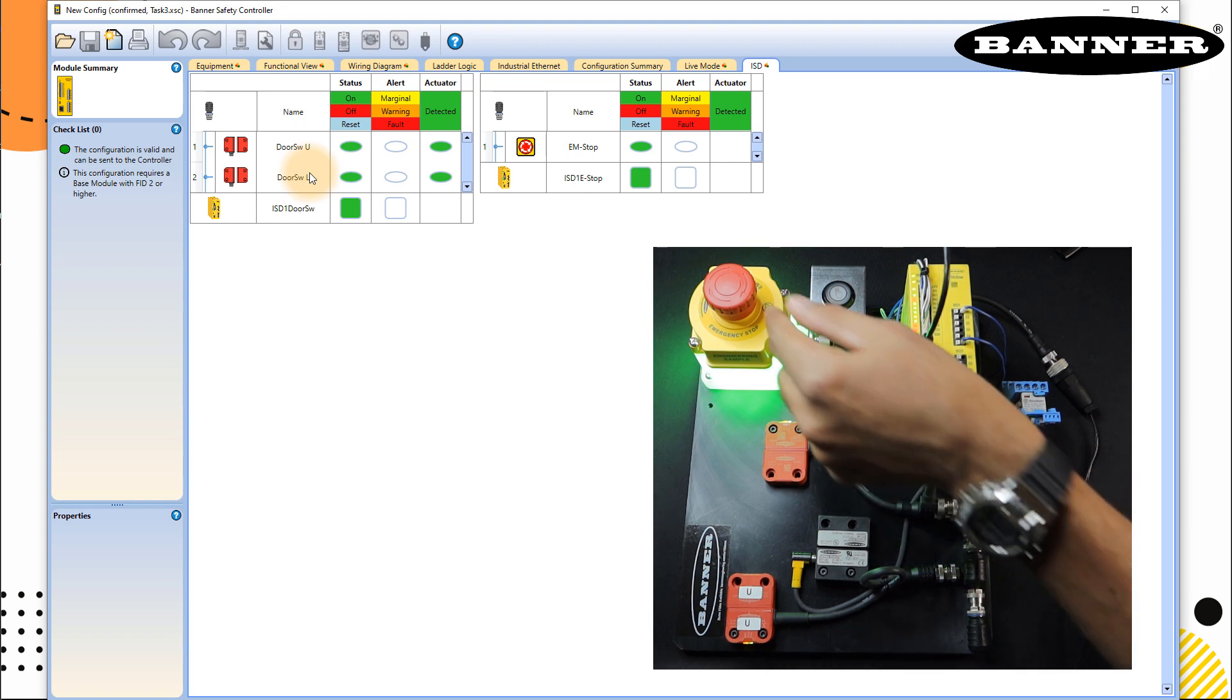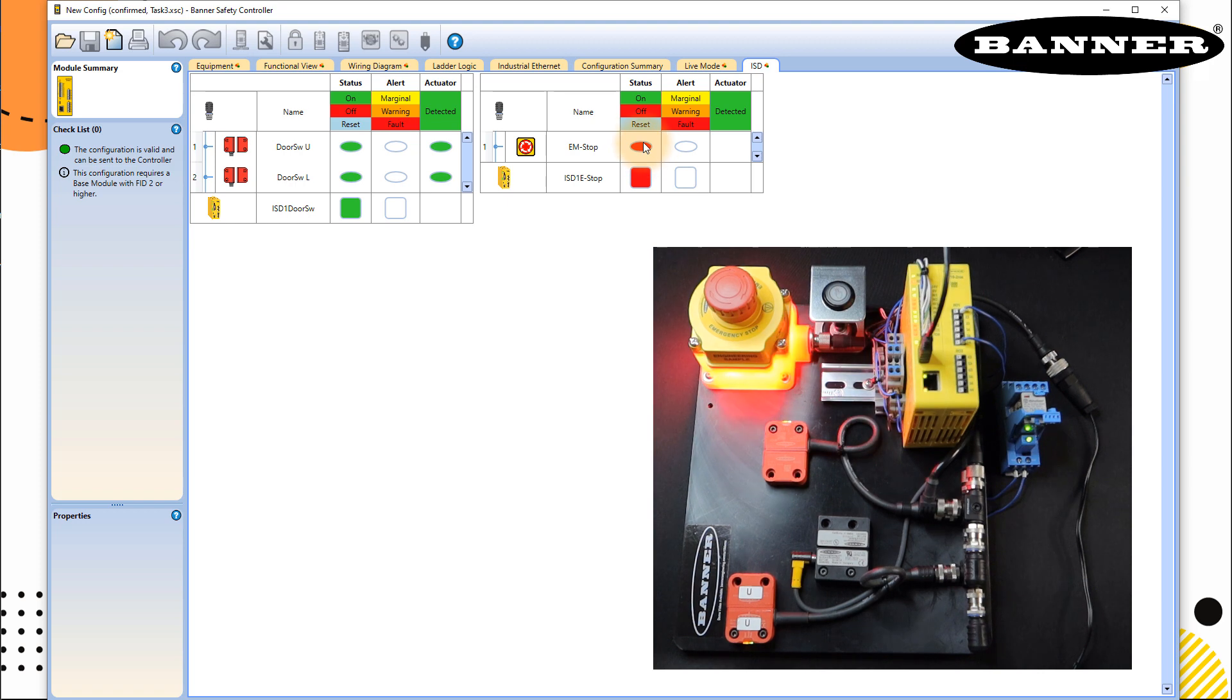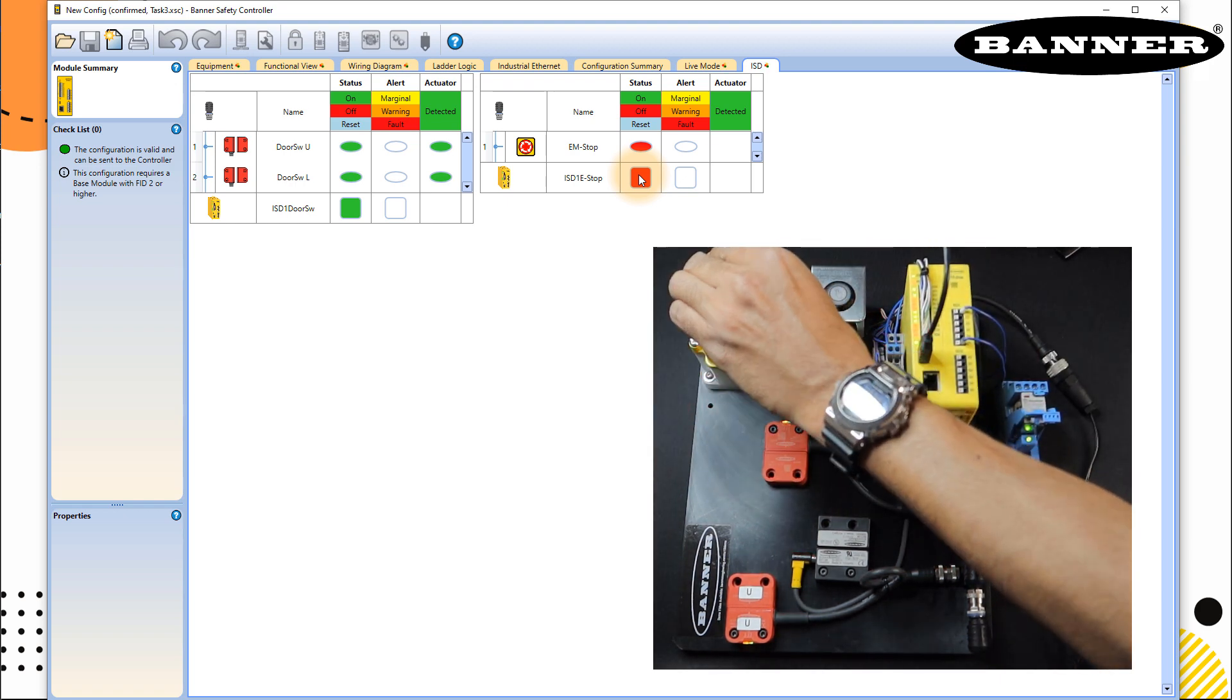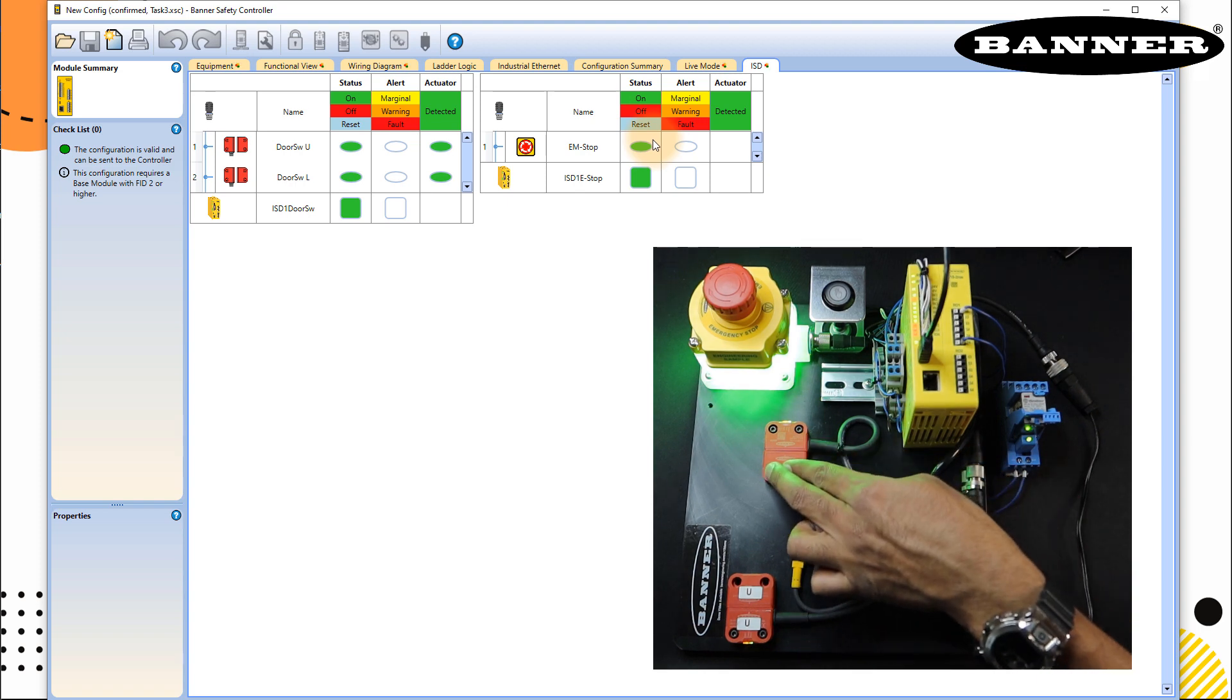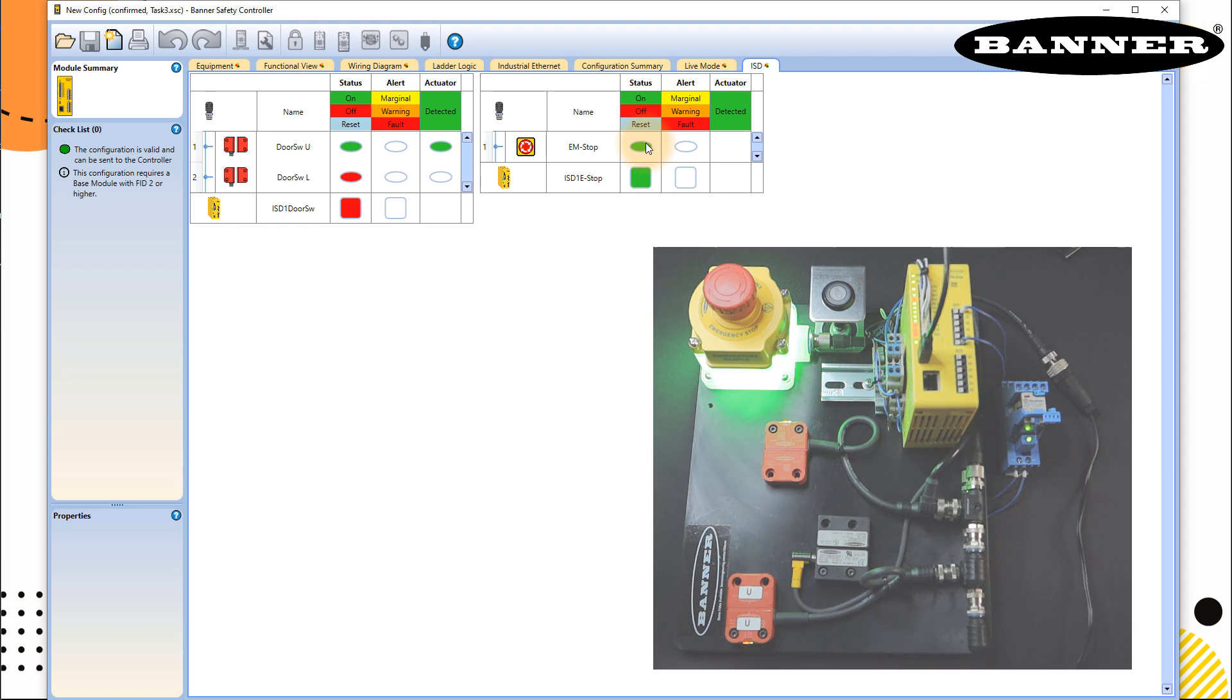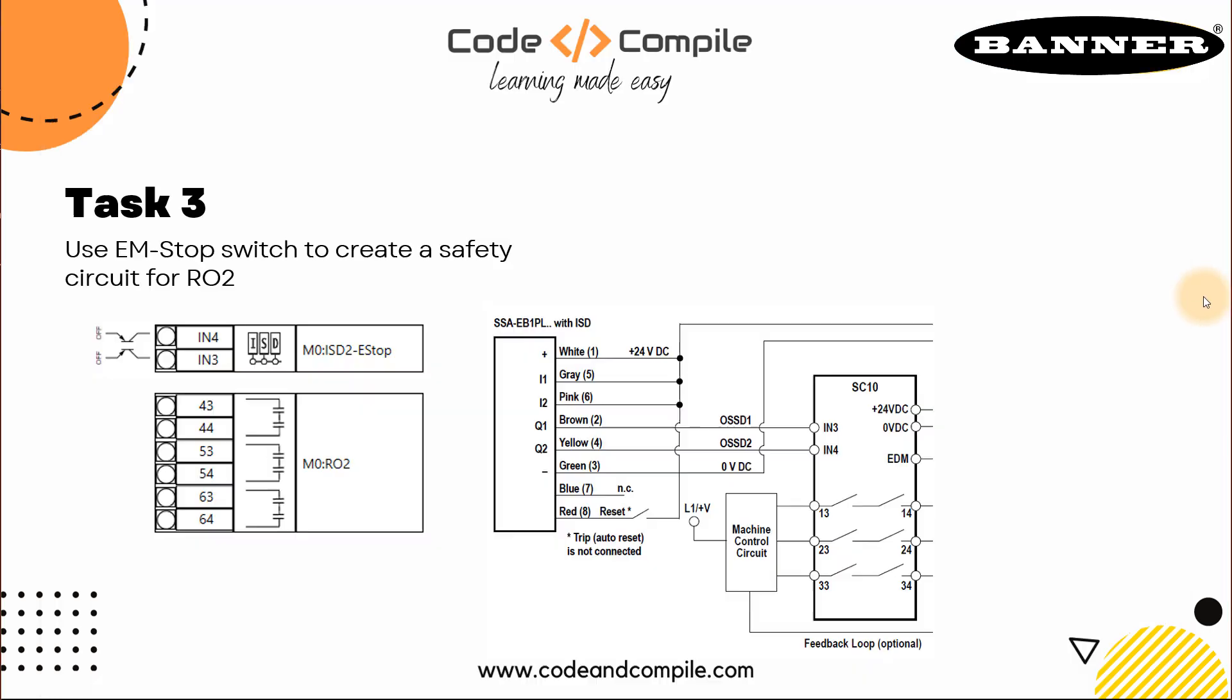Once again, if you press the E stop here, you will see the signal in the E stop is getting red. So ISD chain is false and my RO2 is false. I can release it to see the status back on my software. Similarly here, I can also break the loop and go back to my outputs. So this was the idea of our task 3, in which we just have to connect EM stop to RO2.